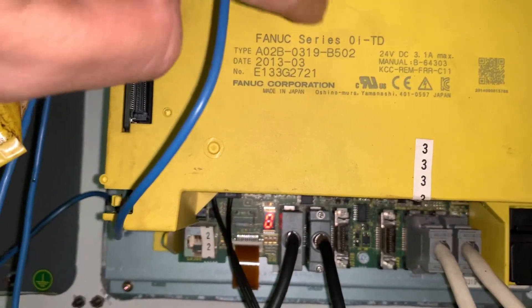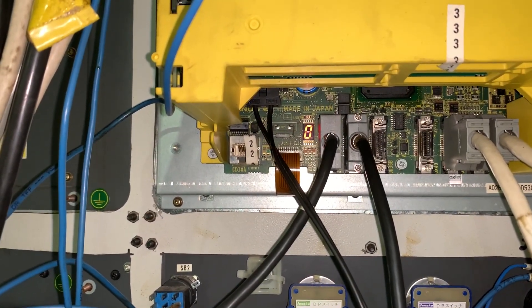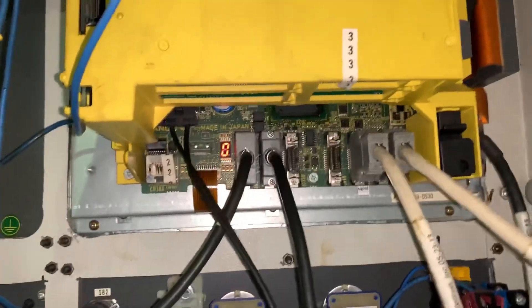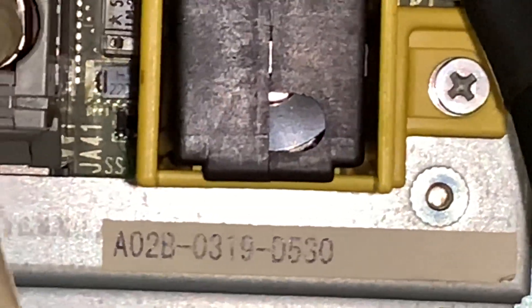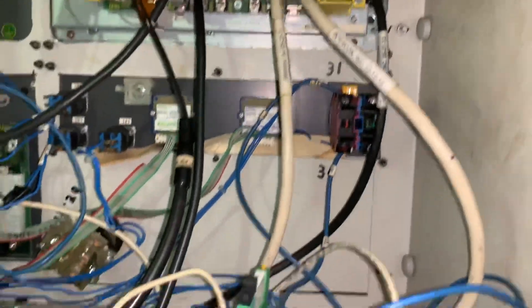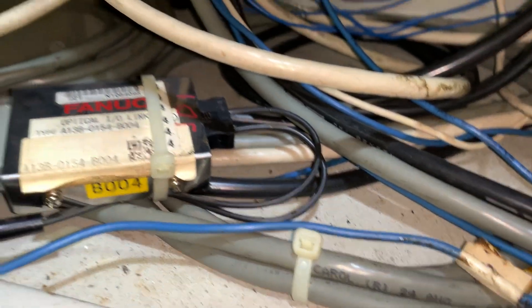If you have a machine with Fanuc Series 0i-TD CNC and you have an alarm — a spindle alarm — SP1229, SP1246, or SP9120, most likely it's going to be a communication error due to the communication cable. We have a serial spindle, so the spindle is connected to the JA41 port on the CPU, and this cable goes to the adapter optical IO link, and from here you have a fiber optic cable that runs to the spindle drive unit.